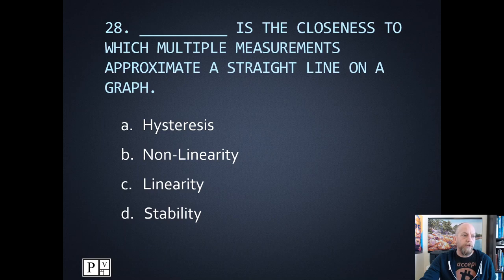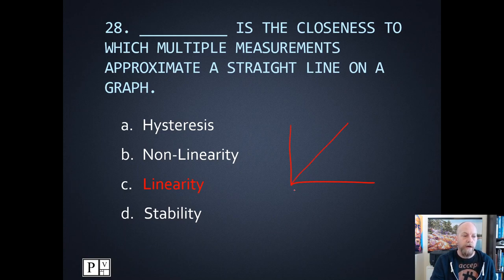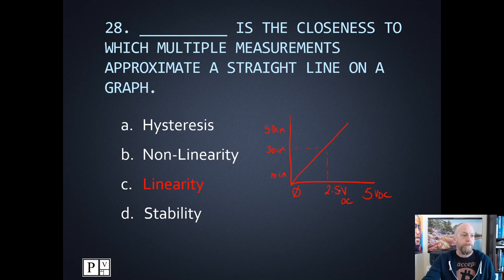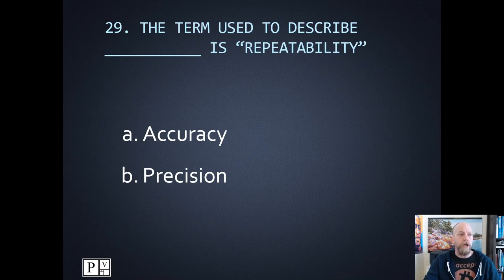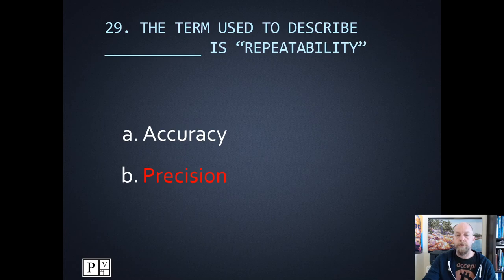Number twenty-eight: which one is closest to describing when multiple measurements approximate a straight line on a graph? Straight line on a graph means a linear output. In the lab, we had our level going from 10 to 50 centimeters with a zero to five volt DC output, and we had a nice linear relationship — at 50% being 30 centimeters, we got 2.5 volts DC out. Number twenty-nine: which one is the term to describe repeatability? Every time you repeat a sensor measurement and it gives you the same answer, that means it's precise. Repeatability and precision are the same thing.